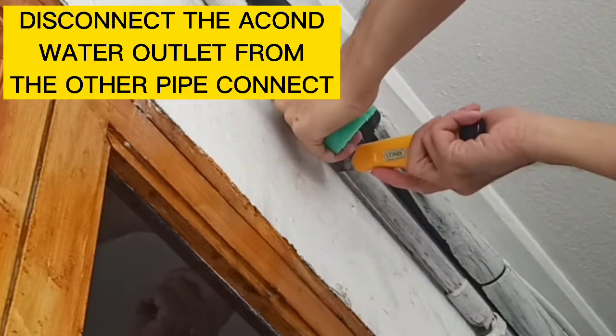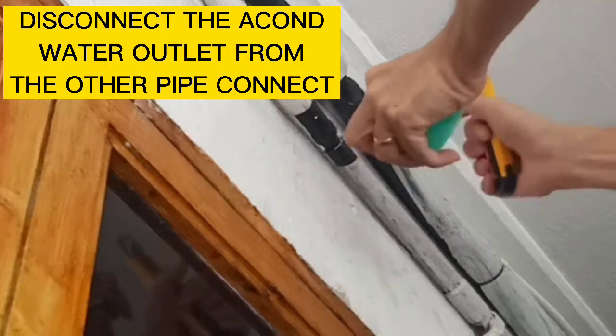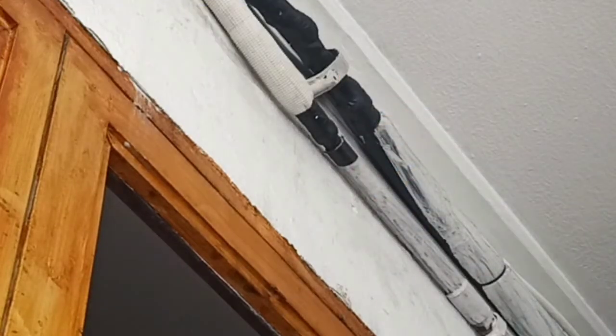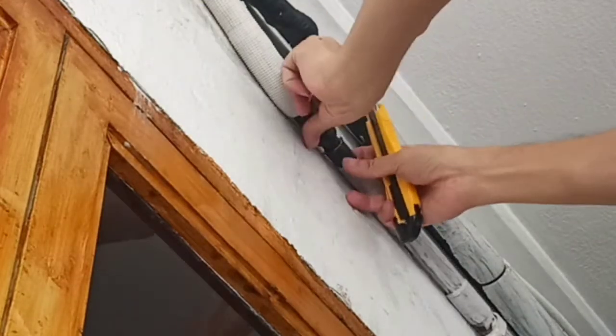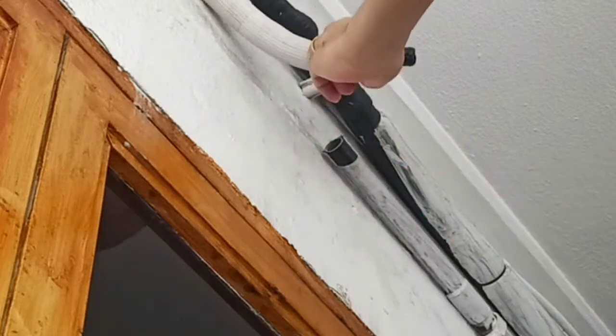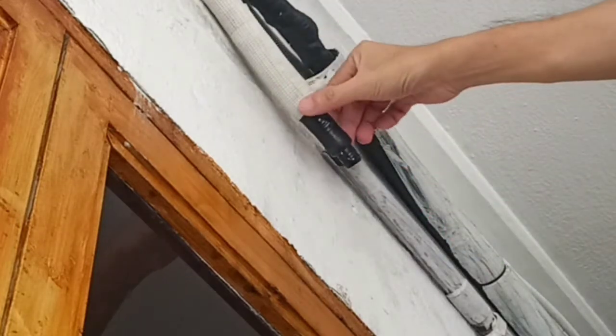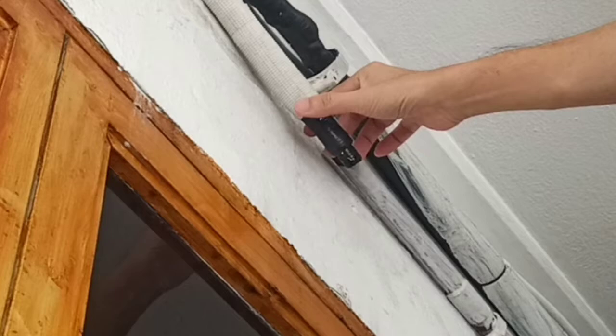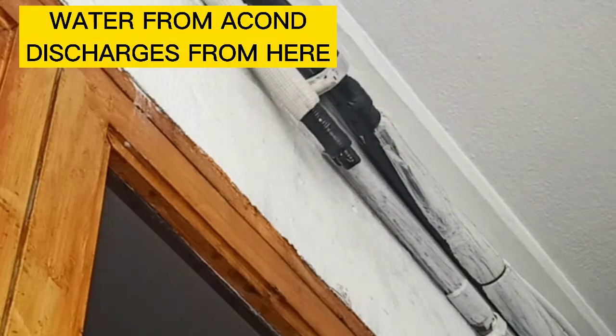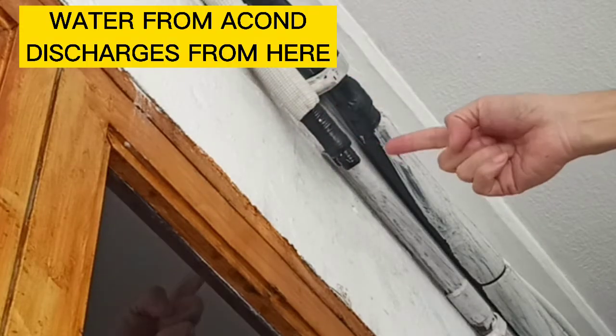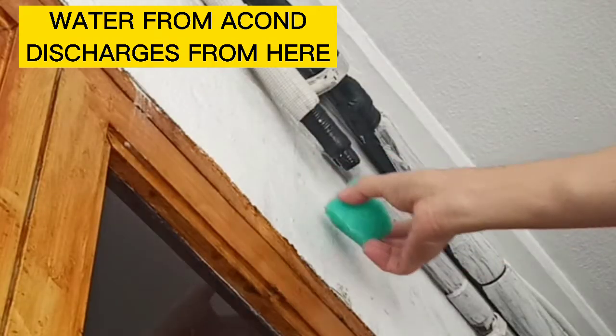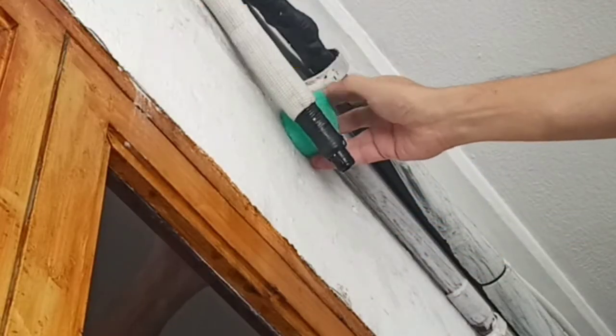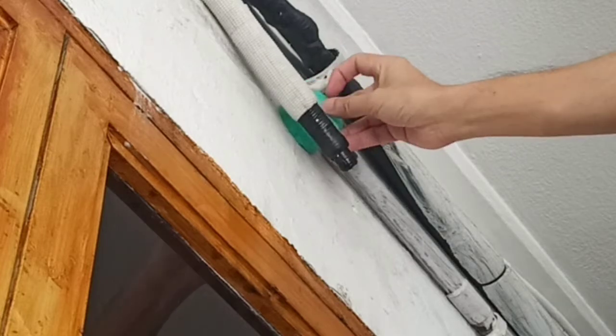So what you do is disconnect the joint, pull out the aircon unit water drain pipe, and the water will come out from there. Now this drain pipe is the one that's causing the water to discharge slowly because of it being clogged up from the inside.